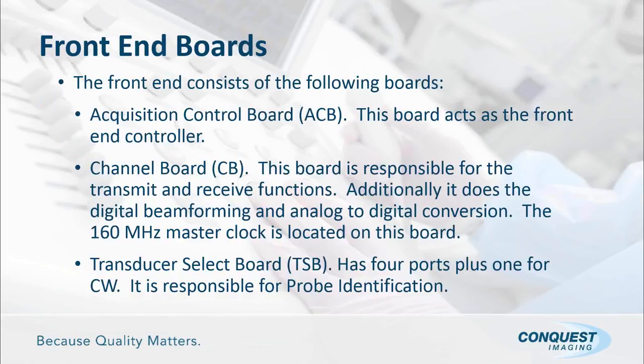There's really three boards that set up your front end. The acquisition control board, and for those of you who have worked on ultrasound or even attended my class, the acquisition control board is what we call the front end controller. Every system has a board that accomplishes this. And what's a front end controller? It simply sets up the front end in the appropriate manner for the probe type, the frequency, whatever functionality the operator selects. It tells the front end how to set up. It tells it what probe I want selected. So it acts just as it says, front end controller. If you hear the word acquisition, that should mean front end to you. That means that's where we're acquiring the signal. So acquisition control board, front end controller.